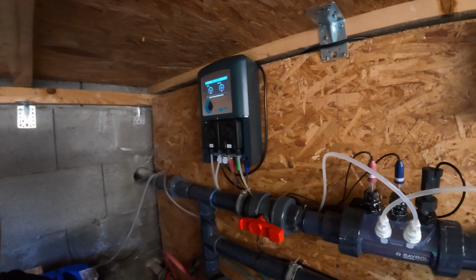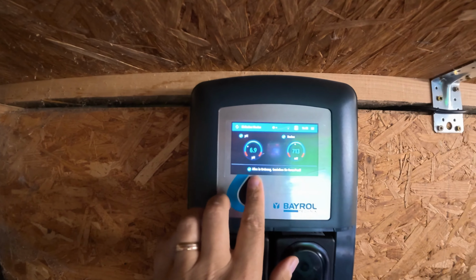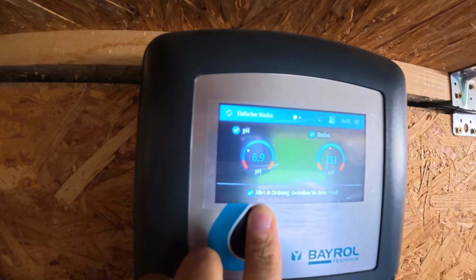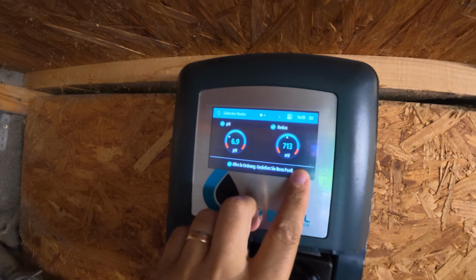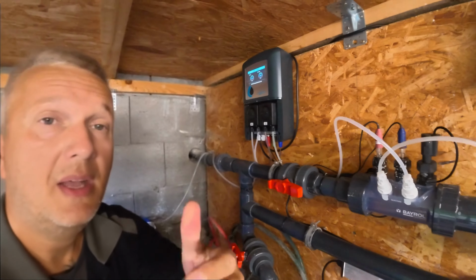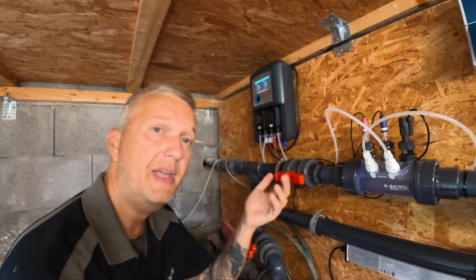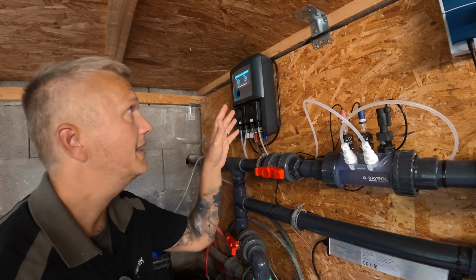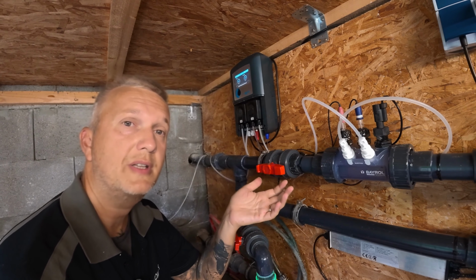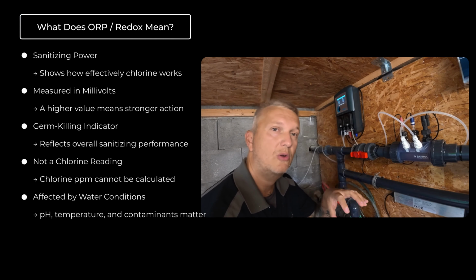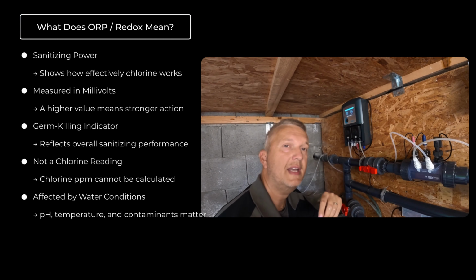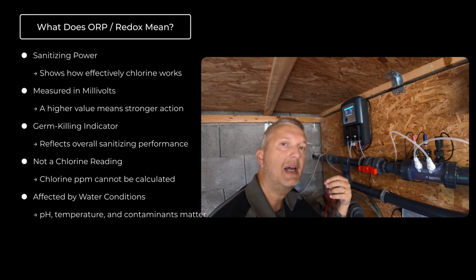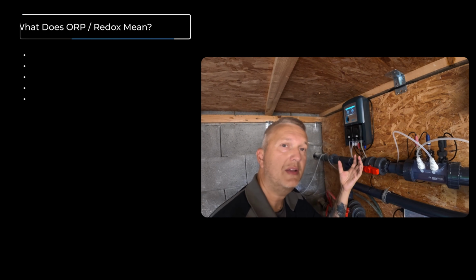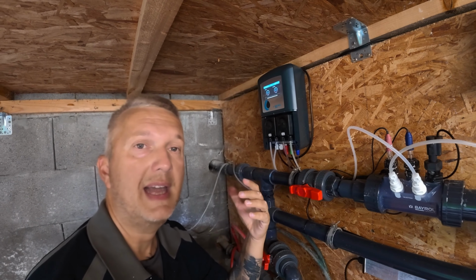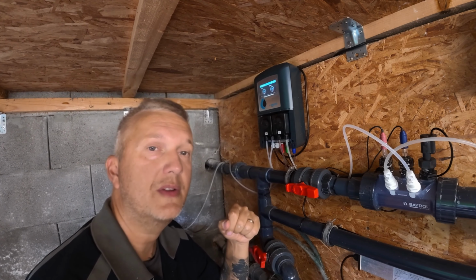The system is currently running, everything in the green zone with a pH value of 6.9 and a redox value of 713. Neither is optimal yet. The pH value should be 7.2, the redox value should be 720, because the redox value doesn't indicate the actual chlorine in the water, but the oxidation capacity, meaning the ability to kill germs, read via electrical voltage. 720 millivolts should be the goal.